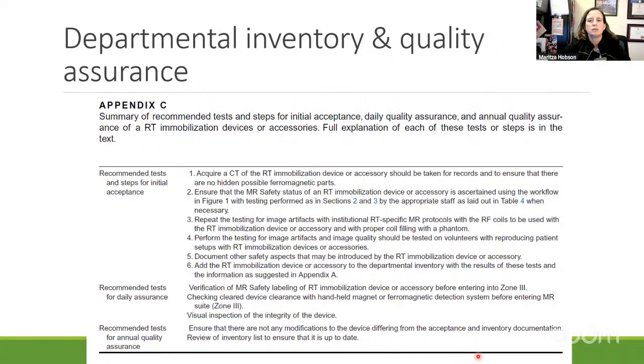Then Appendix C is a summary of the recommended tests and steps for initial acceptance, daily QA, and annual QA of your RT immobilization devices and accessories you'll use in the MR environment. We wanted to highlight that when first accepting an RT immobilization device or accessory, an X-ray or CT should be acquired before it enters the MR environment to ensure there are no metallic components. This goes back to the point that MR unsafe devices can look extremely similar to MR safe or conditional devices. So the wrong device could be sent to you, even if it could have been labeled. It's just like a sanity check.